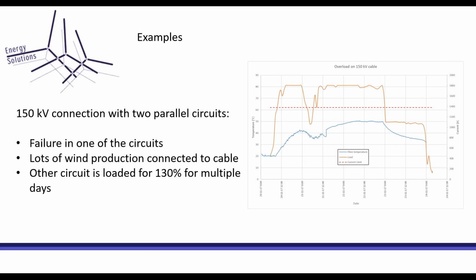avoid having extra costs to reduce the power. From the cable point of view, the load could even have been higher, but in practice there can also be other parts in the grid that limit the current. So in this case, the cable was not the limit. You can also have the opposite of the additional rating that you can have.